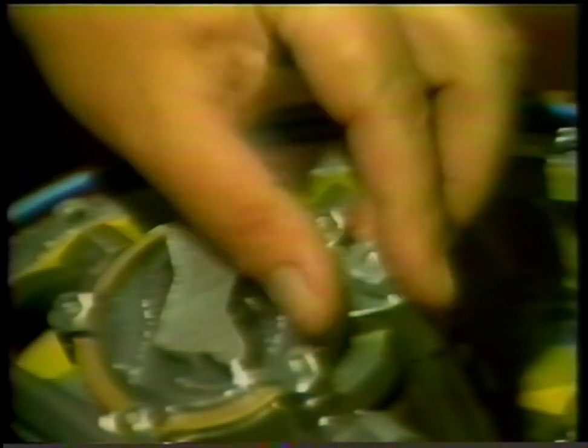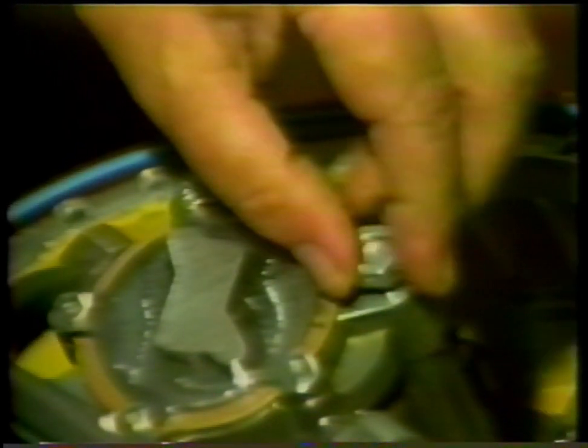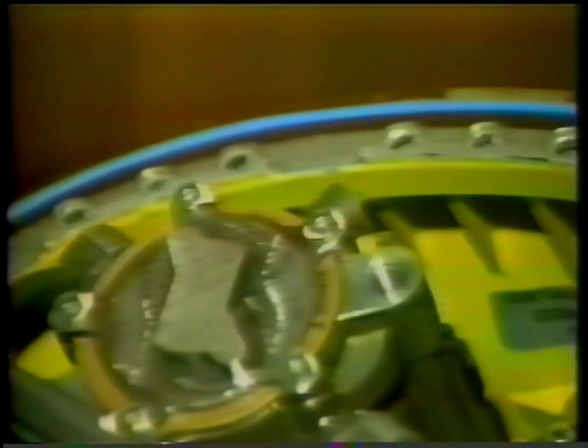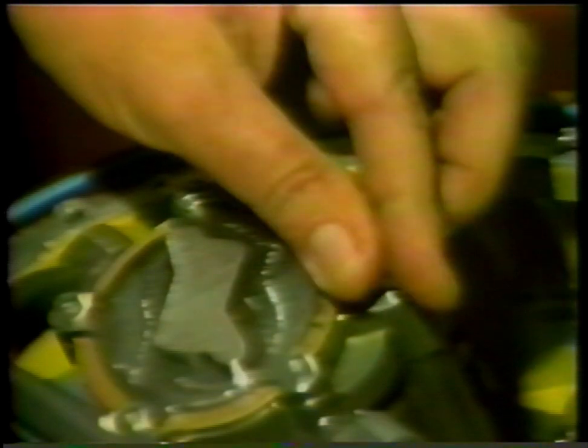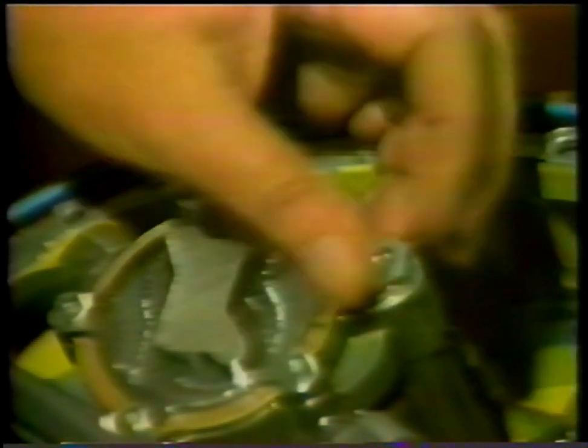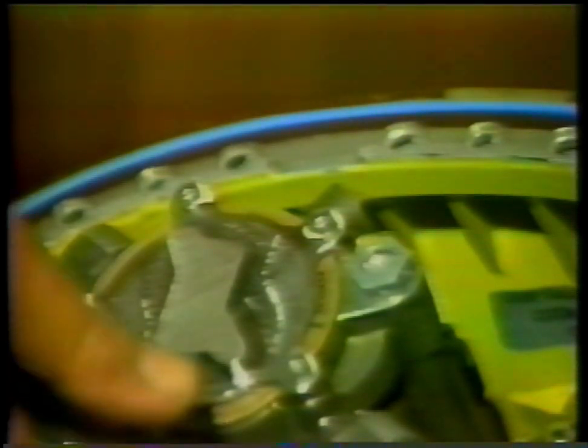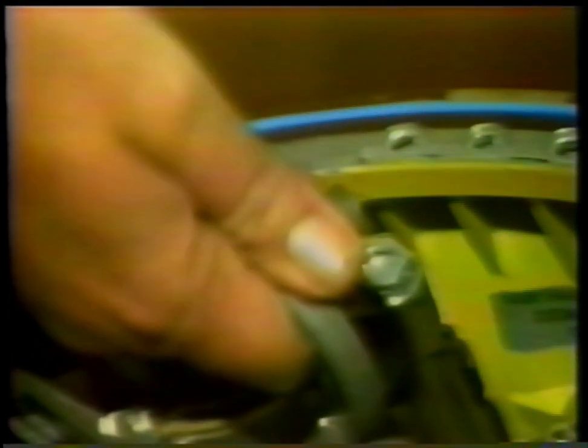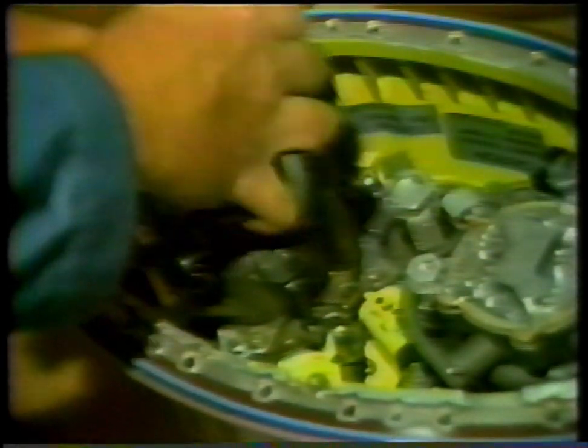If more than a quart of fuel drains from the plug, it indicates that the sleeve did not seat properly and that fuel is now draining from the tank. Stop. Don't remove the pump. Reinstall the drain plug. Then reseat the pump and sleeve. You will have to drain this fuel tank before you can safely remove this pump without a spill.